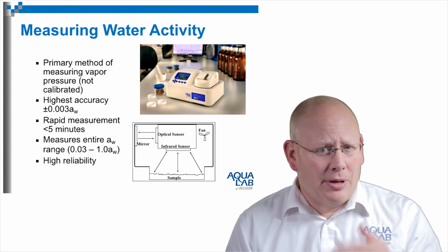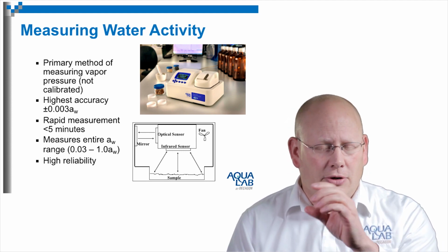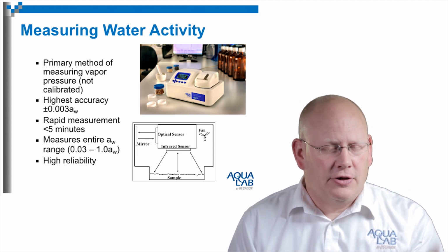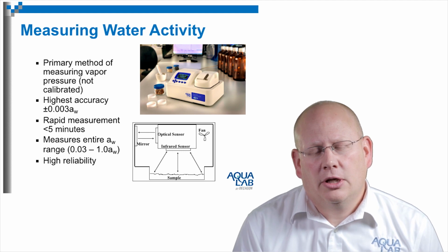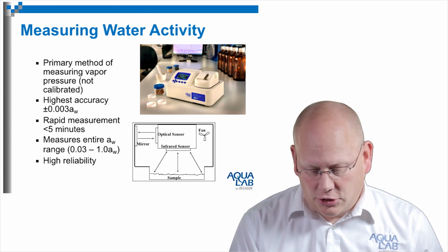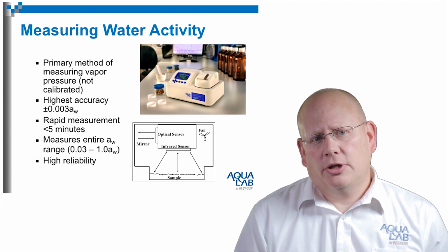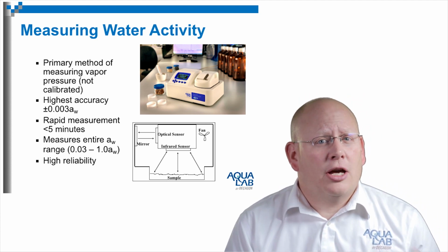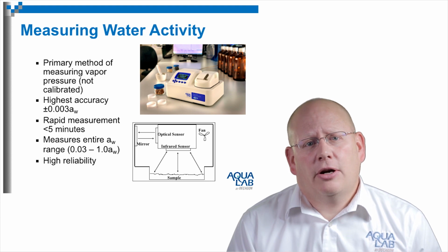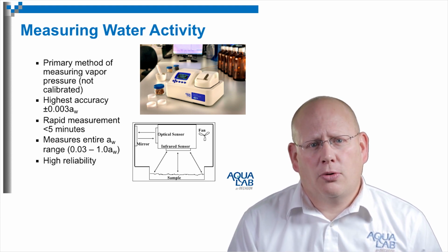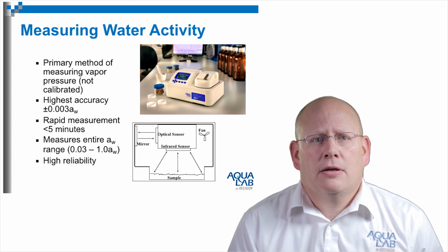Very simple benchtop instrument. You put the sample in, you close the lid, water activity runs, it finishes, and the value is reported onto the screen. And this instrument has the capability of being able to interact with a computer program, which will record the data as well. It also comes complete with Part 11 compliance, administrator controls, password protected. All of those are incorporated into the instrument.